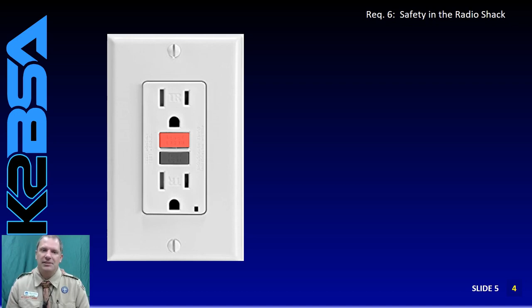You could easily die from a shock before the panel breaker would trip, but a GFCI trips very rapidly with very little current flow to ground. To do this, they have an electronic monitoring circuit that should be tested, which is why there's a test button and reset button on every unit.